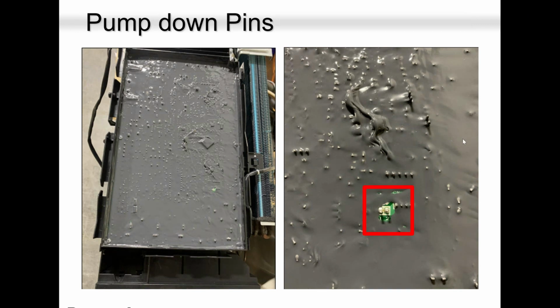If you need to pump down the system, you short those two pins, and the system goes into pump down. That can also tell you that the outer unit is in good shape, because the compressor kicked in and is running and pumping down. So if there's any suspicion about the PCB, indoor or outdoor, you can get your answers there. Okay, guys?